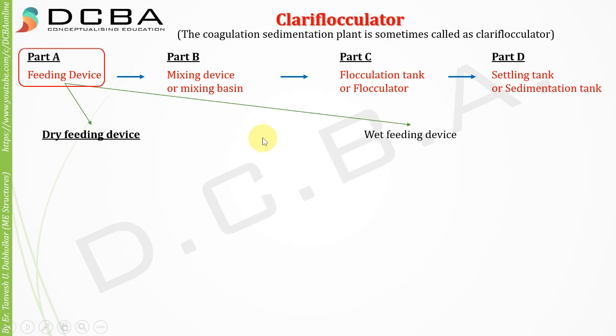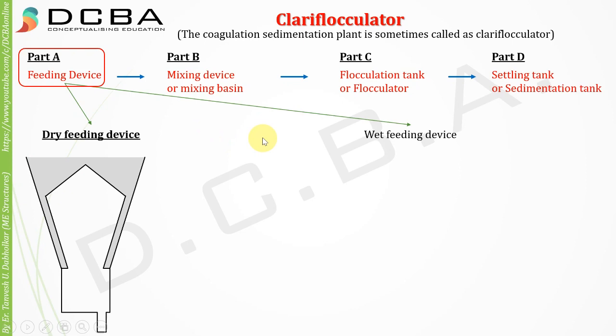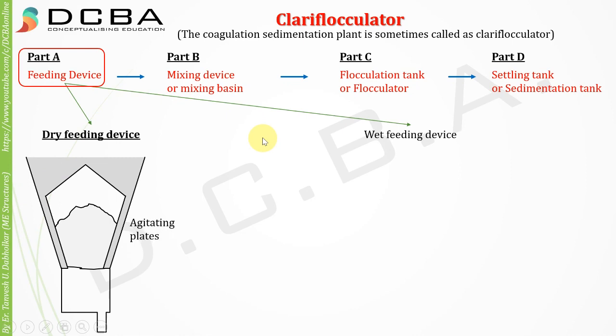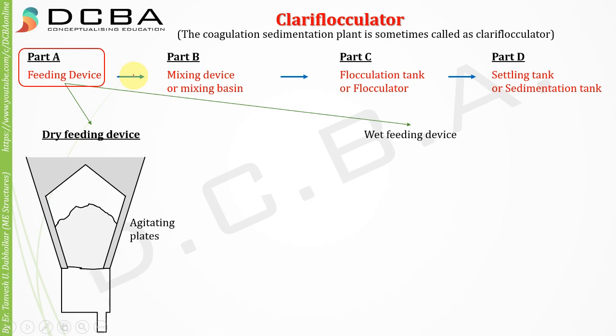In dry feeding, we have a hopper-type arrangement in which the coagulant is put in powder form. The plates on the sides can be vibrated or agitated so that the coagulant in powder form can smoothly drop down. There is also a toothed wheel here — as it rotates, the coagulant powder that falls down is delivered to the raw water.